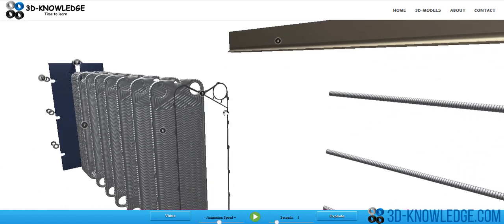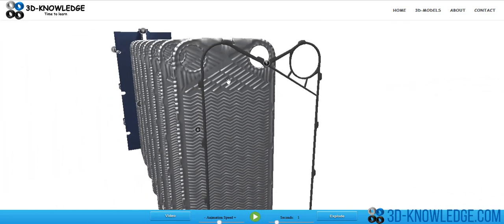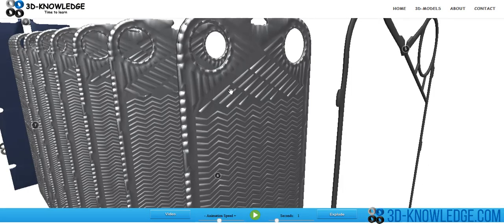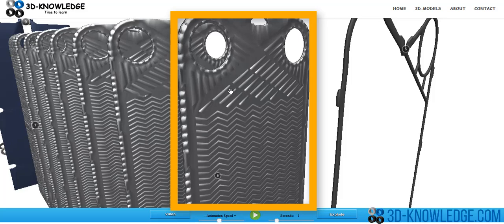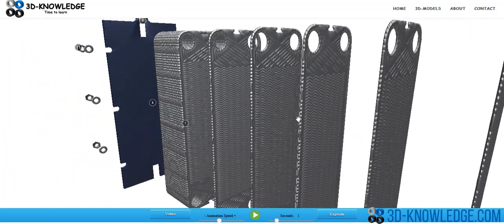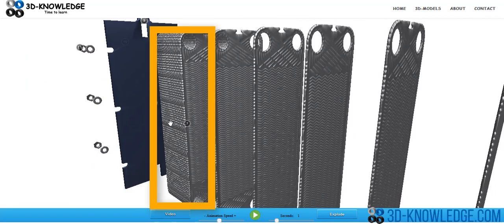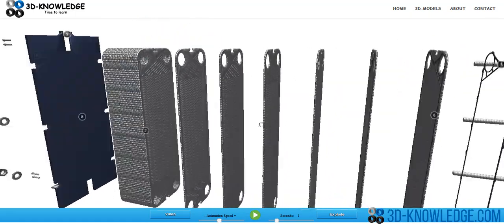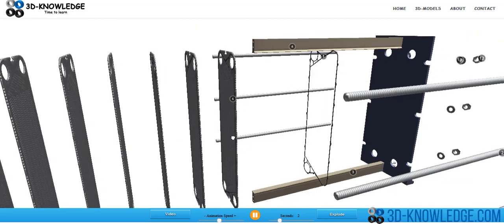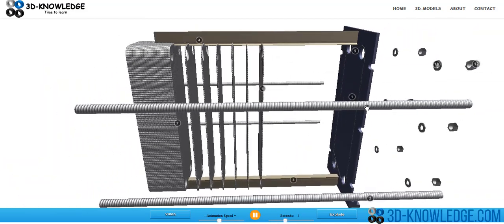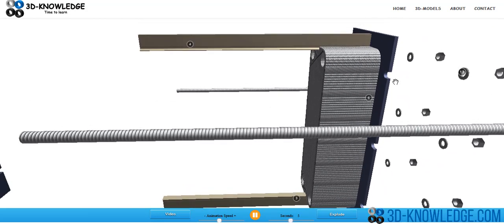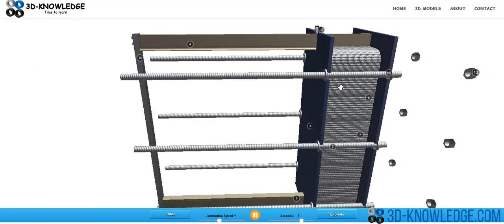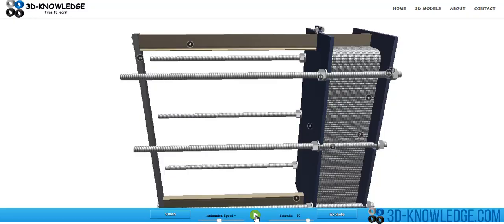Going further, we can see a clamping bar on the top, then a guide bar, and further in we can see a black gasket — it's actually made of nitrile rubber. Behind it we have a corrugated metal plate, and this is where the plate type heat exchanger gets its name. Further back we have more plates — this is the plate stack, which is what it looks like when all the plates are pressed together. There will be another end cover here which is removable, and everything gets pressed together. The clamping bar screw threads go into holes on the right-hand side and it's all clamped together to a certain torque using a torque wrench.